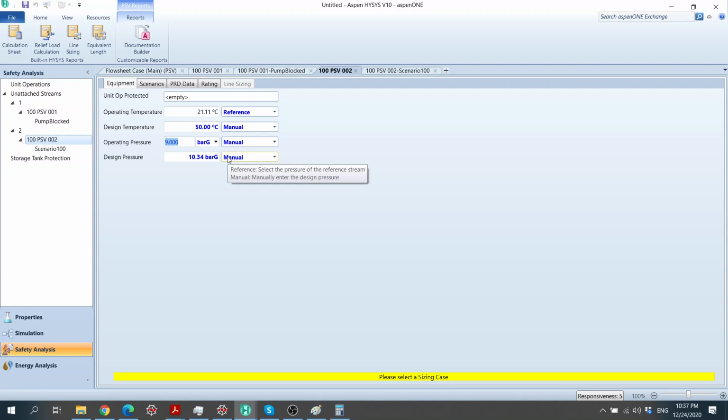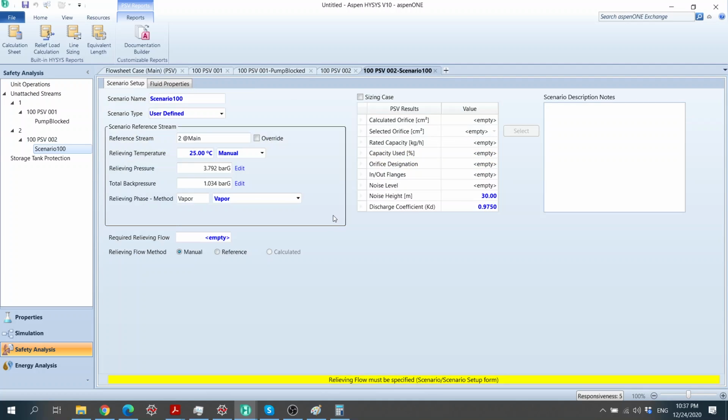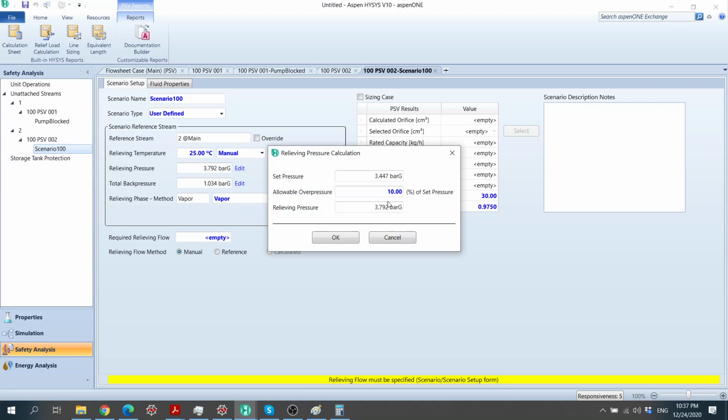50. So operating pressure is then, let's make it, if the release is 50 psig, and then this is then, let's check 3. So we will release at 344. Set pressure at 344, right?